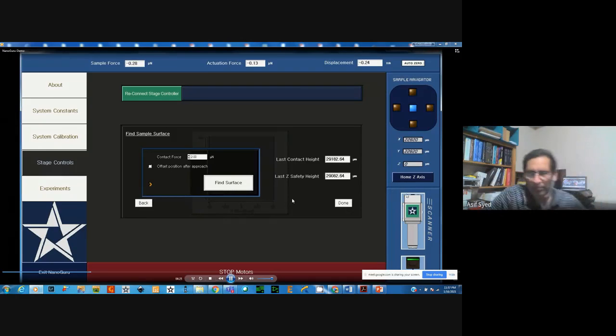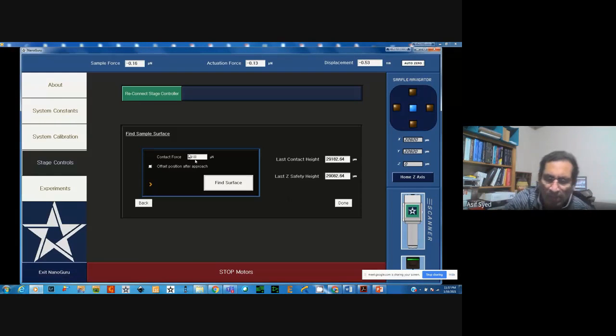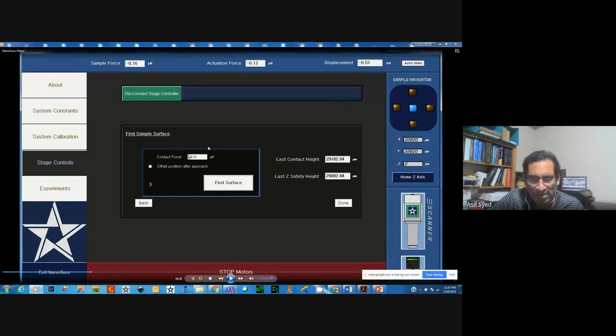Now in this window, you can see that certain parameters need to be put in. The important parameter is the contact force. Basically, as the tip makes contact with the sample surface, it has to maintain a certain amount of force. That is the force we give here as the contact force. So when it makes contact and feels that 2 micronewton force, it will stop. Okay. So when you put the number there and then you run, it's a 2 micronewton force.